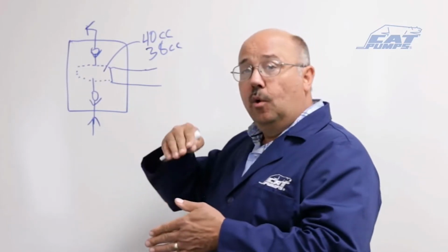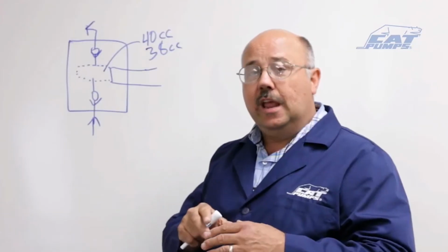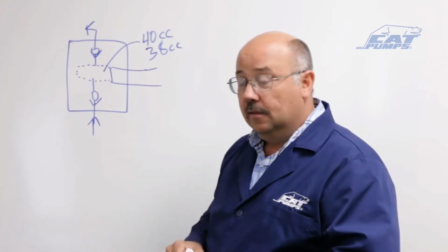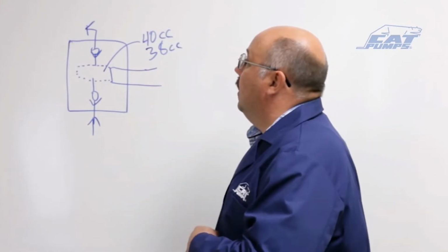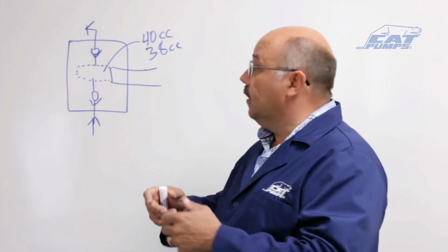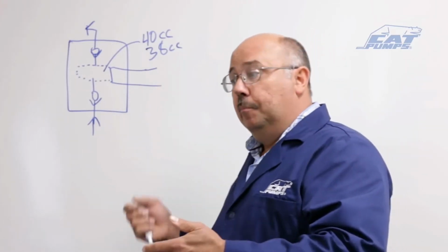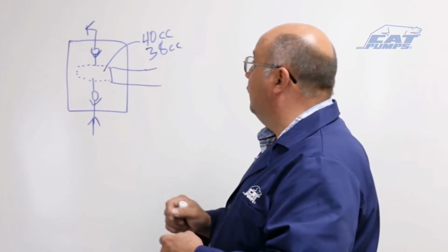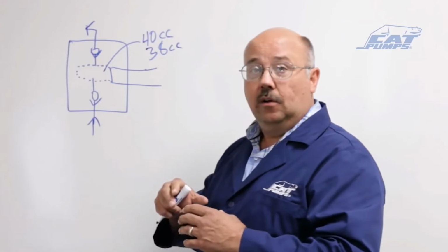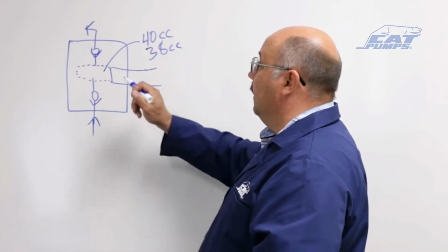Well, what happens is you get a low pressure regime in some part of this pumping chamber, and it will change a few drops of the water from liquid phase to a gas phase. So it's changing the state of the fluid. You're taking it from liquid to a gas on the retraction, and then on the forward stroke you're pushing it back from gas to liquid. Changing the phase is a violent reaction, and it's called cavitation, or there's an implosion going on in there.